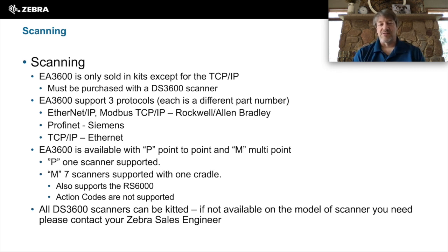The EA3600 comes in several different models. Ethernet IP and Modbus are kitted together as one product for Rockwell Allen Bradley systems. Profinet is for Siemens, and TCP-IP for Ethernet IP. They also come in two different flavors: point-to-point and multipoint. Keep in mind the multipoint is the one that supports up to seven scanners via the wireless cradle, but it does not support action codes. The multipoint is also the one required to support the RS6000.